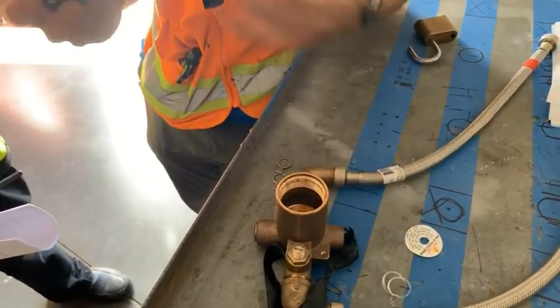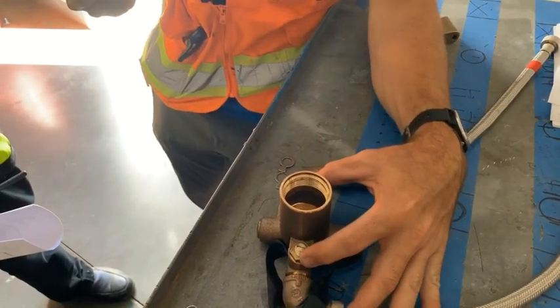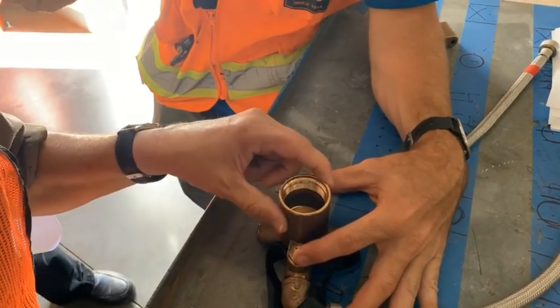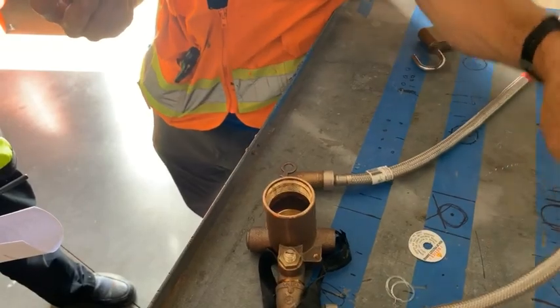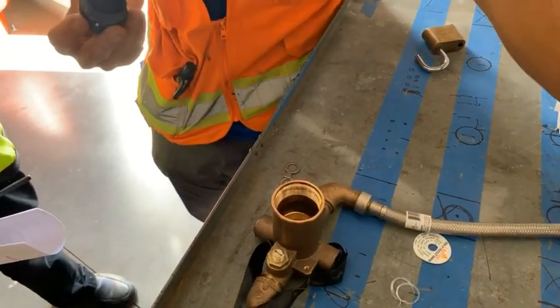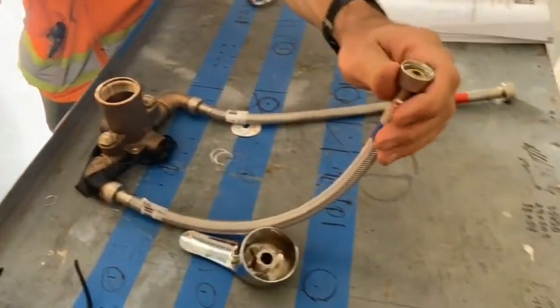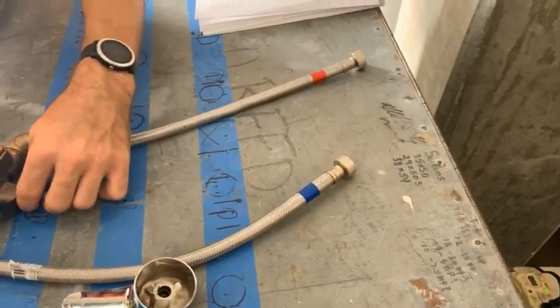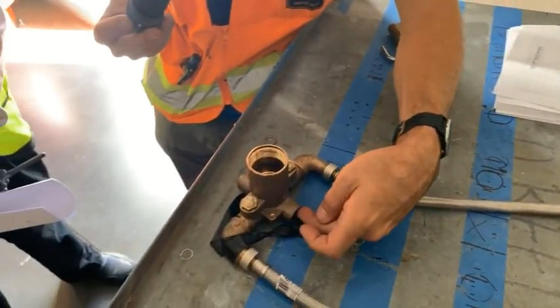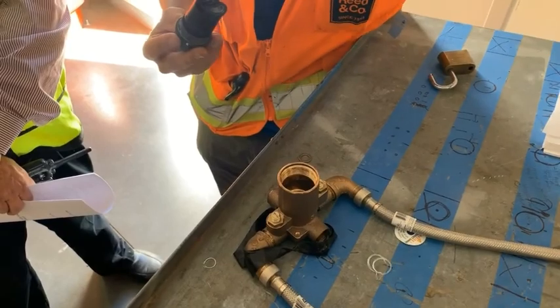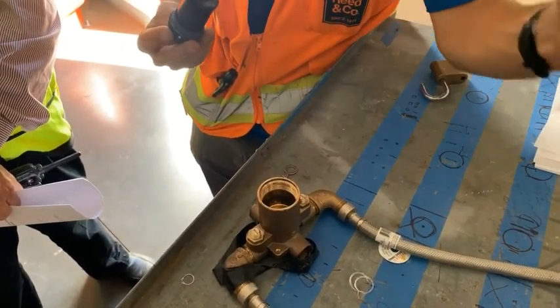But again, before you do all this, we have to make sure we turn these stops off or the main water shutoff valves are off, okay? Because this one's not hooked up. All the units do have these flexes, okay? They go up to a piece of copper. And then there's a SharkBite fitting from the outlet with plastic tubing that runs up to the shower. Yeah, see, I got pictures of that. And yeah, that's all a one-piece thing.